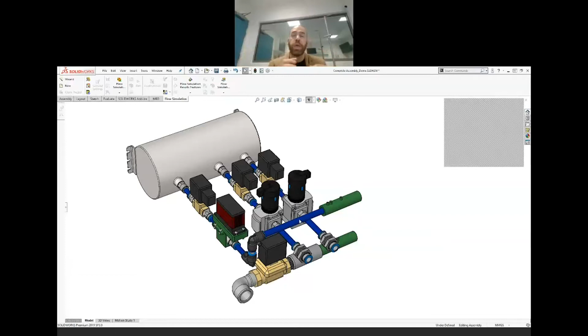The patient inhales, and we have the exhaling. As soon as the patient exhales, the valve that is supplying the air will close, and there is another valve on the exhale part that will open. And this is where we monitor the air going out. When the air coming out reaches a certain point, which is the pressure inside the system, so we're looking at the pressure inside the lungs of the patient, this is typically called the PEEP level. The physicians will call it the PEEP level, which is the minimum pressure that they would love to have inside the lungs of the patient, because if we empty it completely, we could have a collapse of the lungs. So they keep some pressure inside the lungs. So we monitor this pressure, we monitor the flow, and we close the valve at the point to keep the pressure inside the lungs.